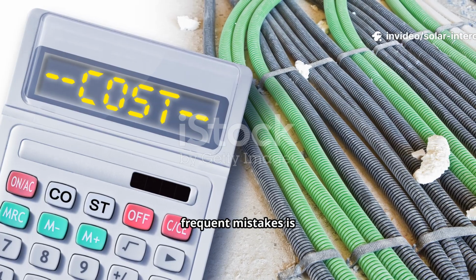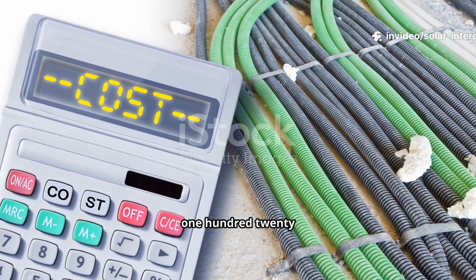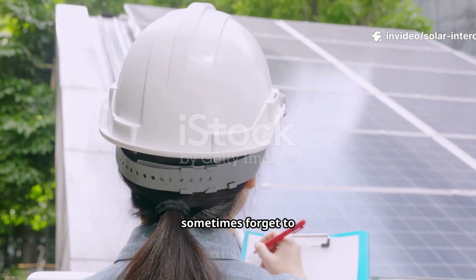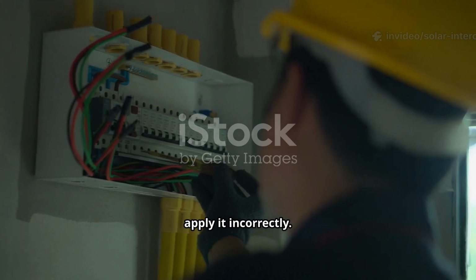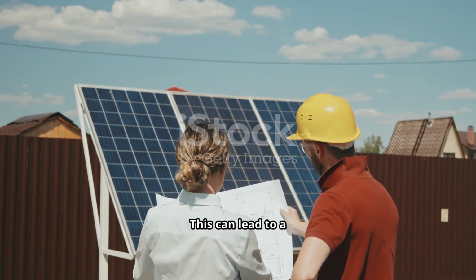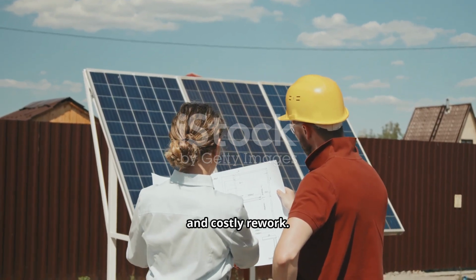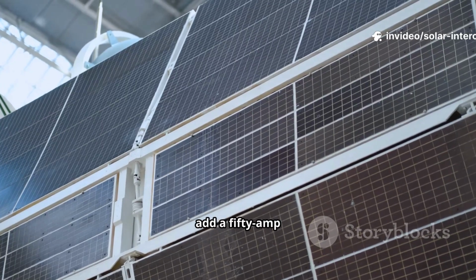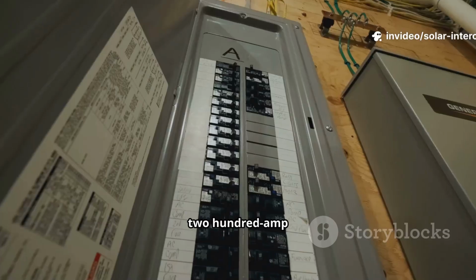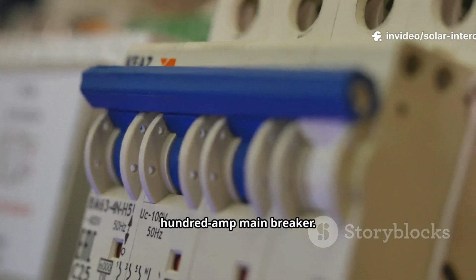One of the most frequent mistakes is miscalculating the 120% rule. Installers sometimes forget to apply this rule or apply it incorrectly. This can lead to a failed inspection and costly rework. For example, an installer might add a 50-amp solar breaker to a 200-amp panel with a 200-amp main breaker.